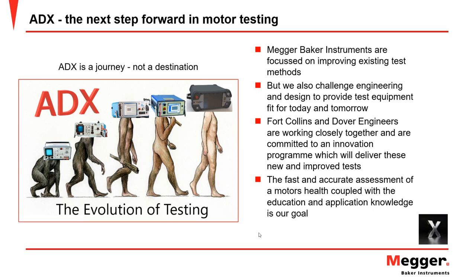Our tester is tiny in comparison for the power of the tester, but we do try to emulate the voltage to see if there's going to be any deterioration of the insulation between the turns and the coils, as well as to ground, but more importantly, between the turns and coils. And the reason for that is because that's the weakest insulation in the electric motor. If you've ever seen winding wire or magnet wire, you will see that there's a thin layer of insulation across there. Now that's all the insulation that we have preventing the turns from touching each other.